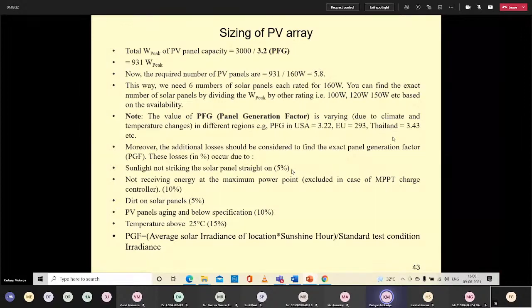But I give you the equation, that the equation for PGF is average solar irradiance of the location into sunshine hour, divided by the standard test condition irradiance. Now, if your place is such that additional losses should be considered to find the exact PGF, which are the losses?